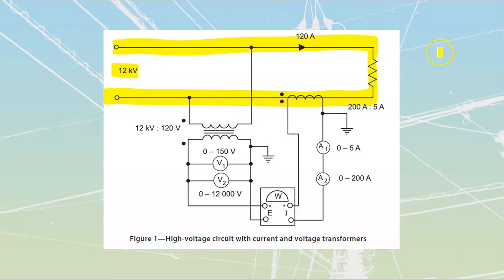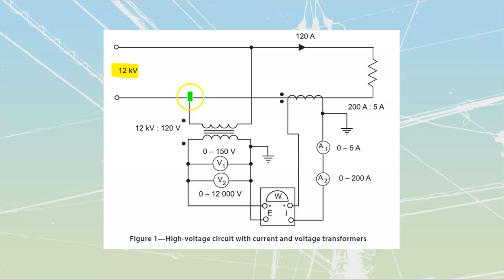be seen as just being a very small load to that system itself. So we're going to designate our primary current path. The next thing that we are going to do is we're going to designate each of our metering paths. My voltmeter is simply connecting across from line to line on my main 12 kV. So we're going to drop from 12 kV down to 120 volts. They could place a capacitive voltage divider inside here if they want it. We could have a cap divider, dropping this thing down, and then we are going to go and split across that, but in some cases it's not going to be necessary. And then my CT is also going to have a primary that is going to be connected in over there, just through the fact that we are bolting on that CT.